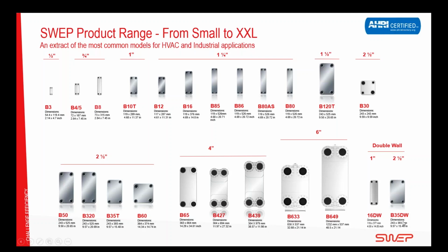And then for double wall, we have a 1 inch model and a 2.5 inch model. And I would like to point out that the SWEP double wall is a double wall all over the plate. It's a double wall here, here, here, and here. Wherever you see on a double wall from SWEP, it's a double wall all over the plate.